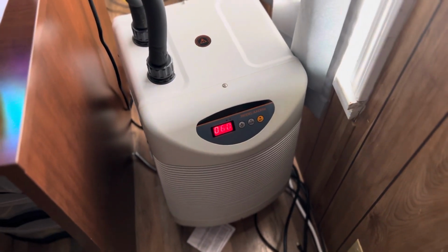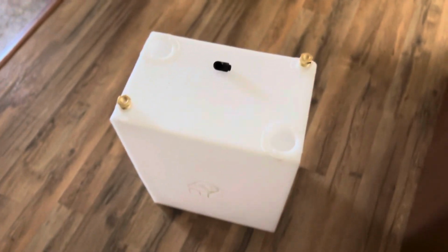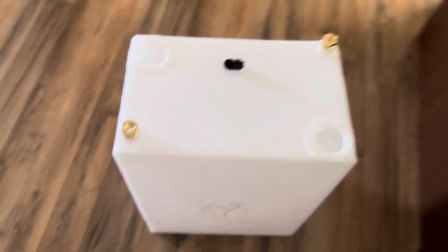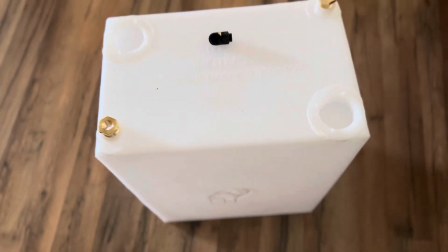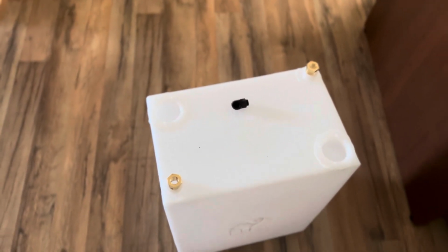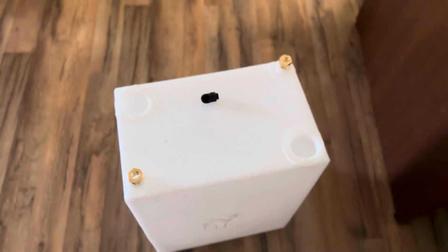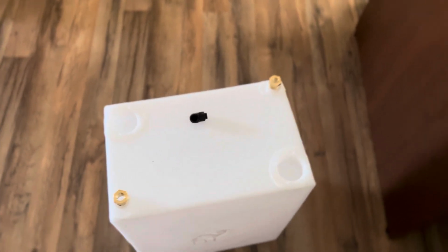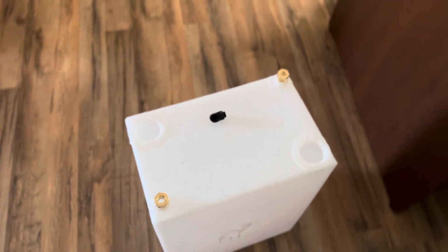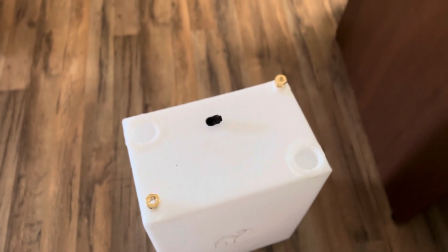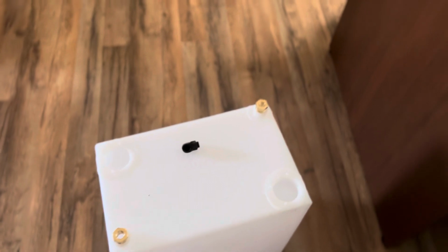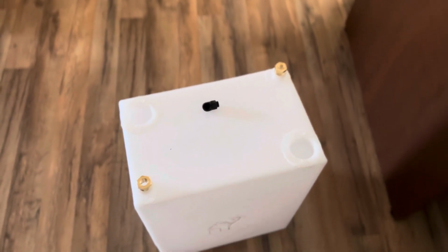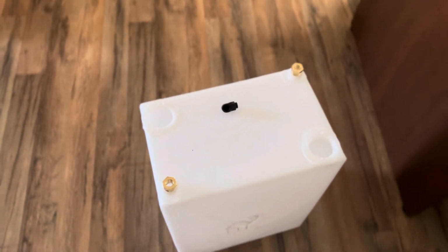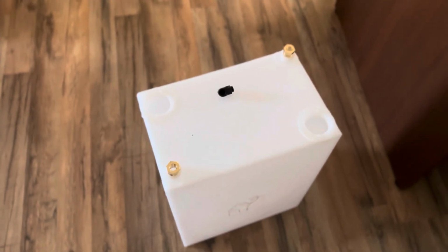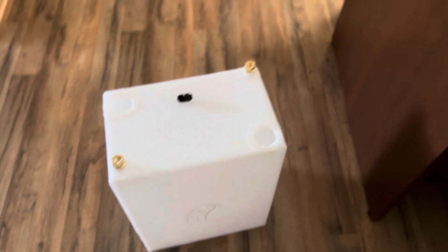The advantage to having a buffer tank is you have this large capacity of water, and this water is all going to be the same temperature as what's in the chiller. So because of this, when your water is set to 15 Celsius and the chiller is like, okay, we're at 15, we're going to turn off, it turns off. Your system stays at 15 Celsius, and then it slowly warms up at a much slower rate. And when it reaches 16, 16.5 Celsius, boom, your chiller has time to recognize it needs to turn back on.